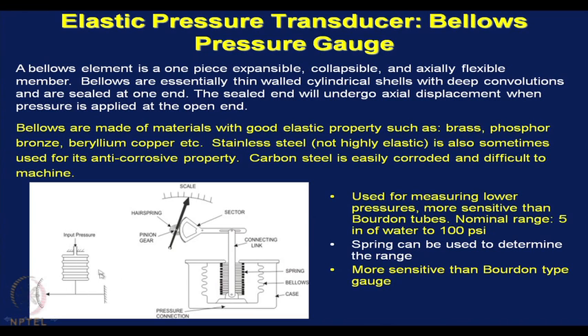This is a schematic of a bellows element. It is essentially a thin-walled cylindrical shell with deep convolutions. It is sealed at one end, and at the other end we can apply the process pressure. If I apply pressure here, the sealed end will undergo axial displacement, which can be read by the deflection of the pointer against this scale.